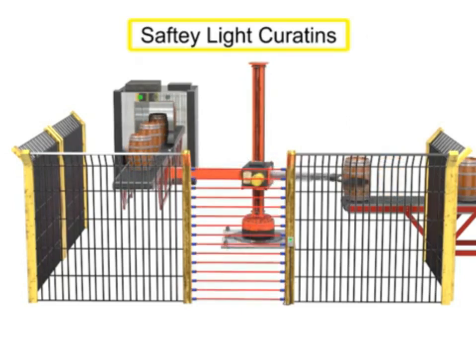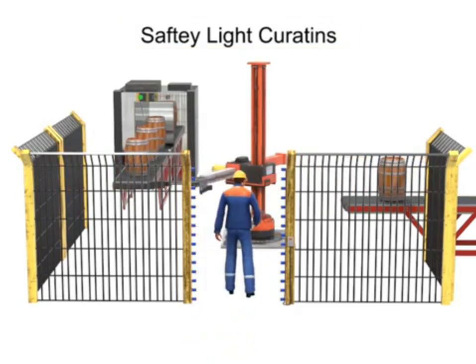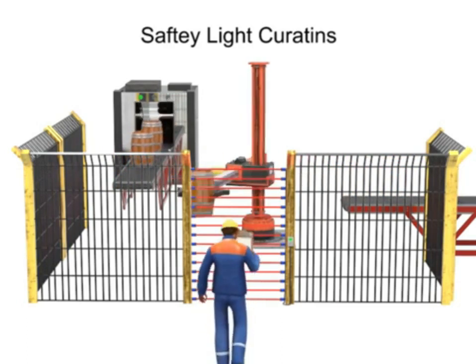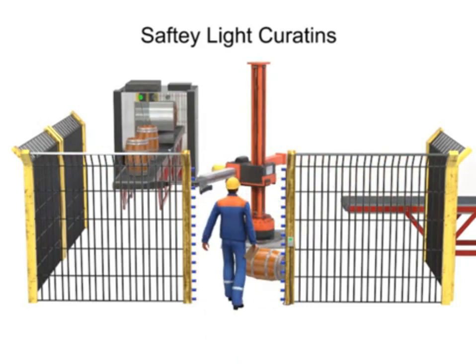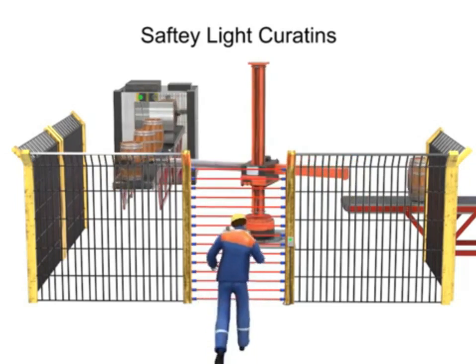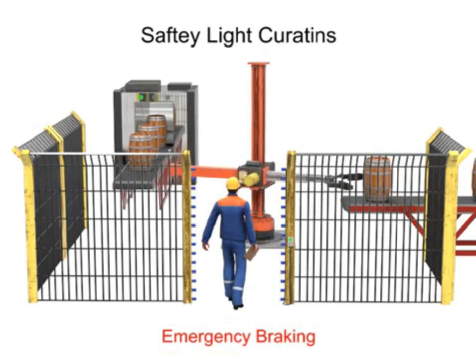Safety light curtains are another type of presence-sensing device. When a person enters the work envelope, the light beam is interrupted, which sends a signal to the robot. For certain work scenarios, sudden stops could cause the work to become uncontained — objects may continue to move even after the robot stops. In these cases, emergency braking of the robot is used in lieu of completely stopping. With emergency braking, the robot slows down work and does not stop suddenly.